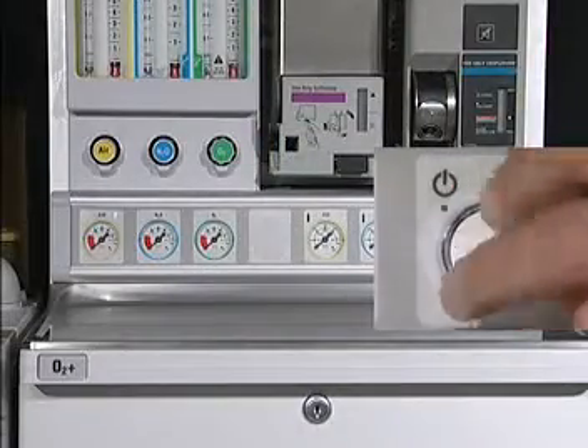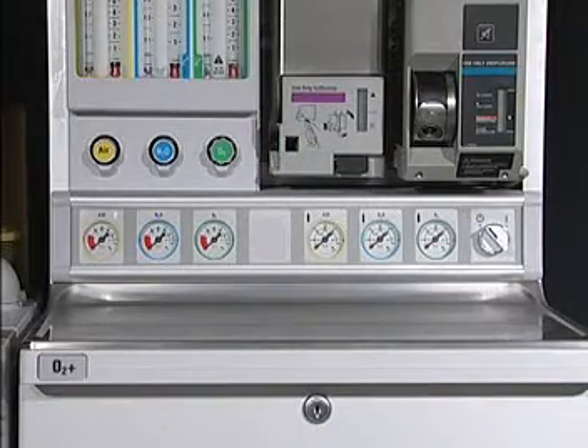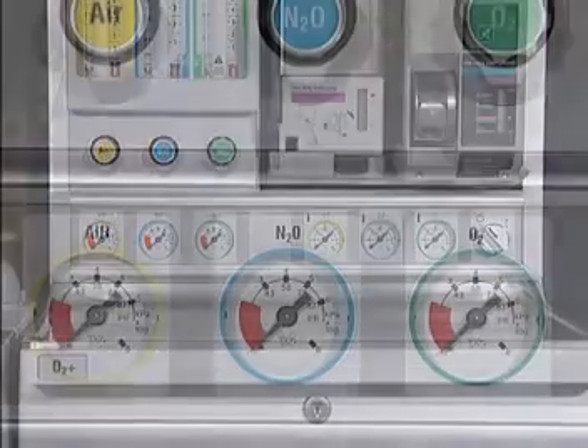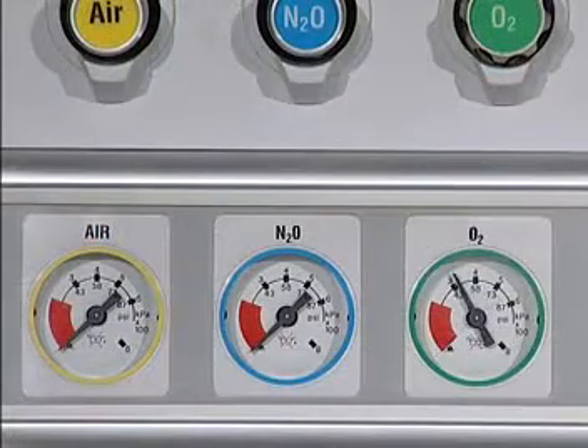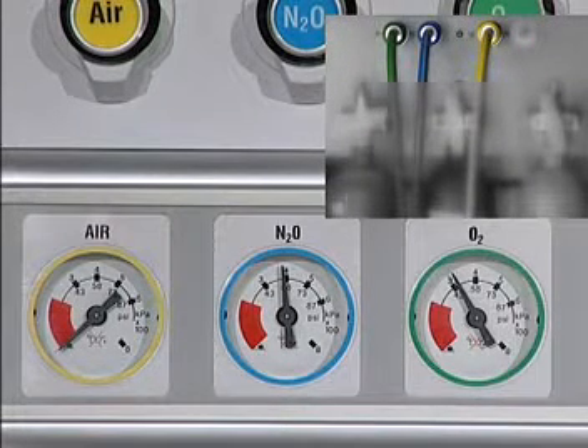The conveniently located on-standby control switches both anesthesia machine pneumatics and ventilator electronics. The term standby is used because of the existence of a battery with an internal battery charger, which may lead to power draw even when not in the on position. The pressure gauges located directly below the flow controls show the pressure of each of the primary source gases, and the gauges located under the vaporizers show the pressures of standby supplies.